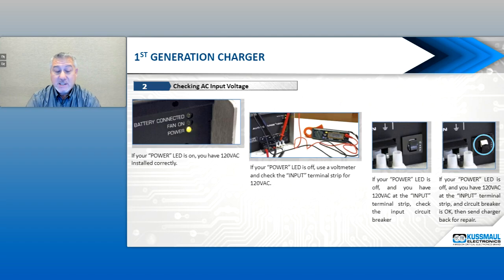It's possible, and I've seen it, where the shoreline comes in, maybe through a Kussmaul auto eject or another plug, and then goes into a junction box. There's power going to the junction box, but no power actually making it to the charger. So if you check that and there's no voltage at the input, double check that wiring.